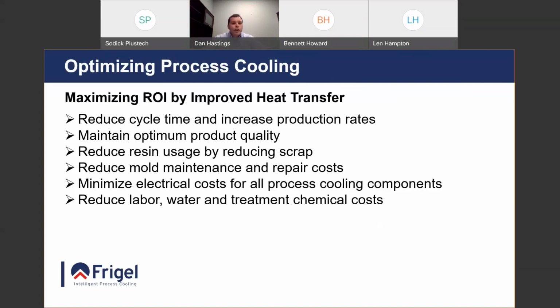Maintain optimum product quality by increasing the flow and pressure to the tool. We're going to get a uniform and low delta T across the mold. This will allow us to provide better quality and repeatability, which will reduce scrap overall. Reduce mold maintenance and repair costs. This is going to touch base on the water quality, keeping your molds clean so they're in service more and not in the maintenance room. Minimize electrical costs for all process cooling components, and reduce labor, water treatment, and chemical costs.